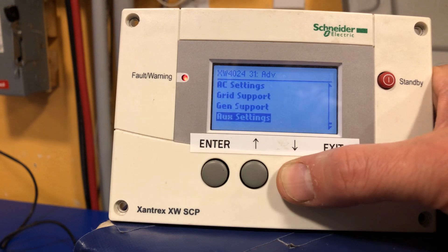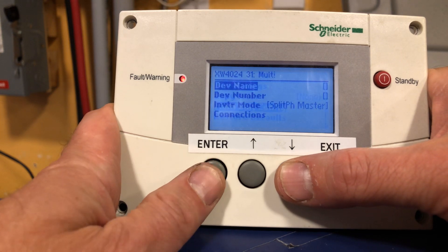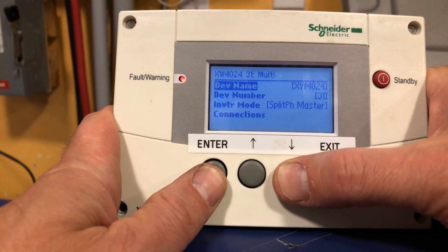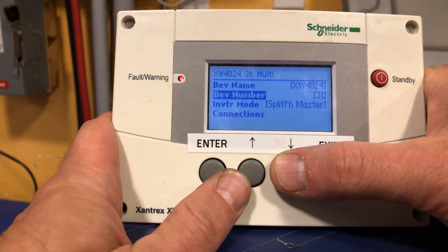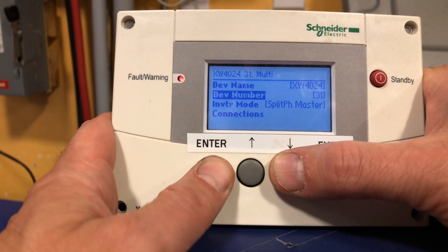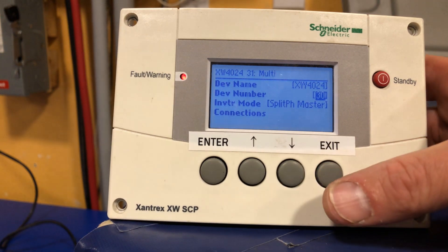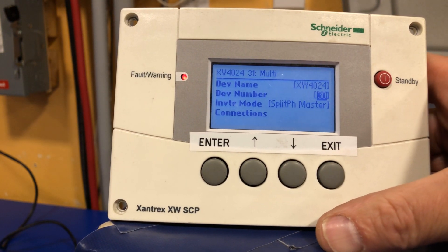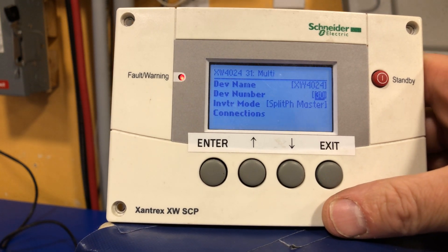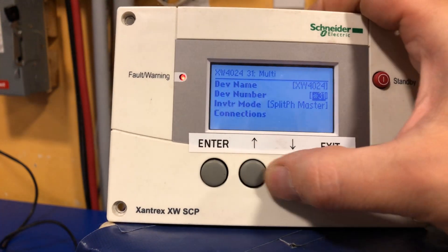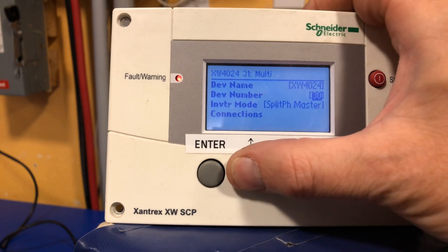I'm going to scroll down to the bottom of this list — multi-unit config. Press enter. Here's the name; I'm not going to change that. I'm just going to press down to highlight the device number. Press enter. Right now is when the system would typically just immediately and unexpectedly go into shutdown, so that's not ideal. Let's disable it first, and then we come in and change the device number to any unique number that you want.